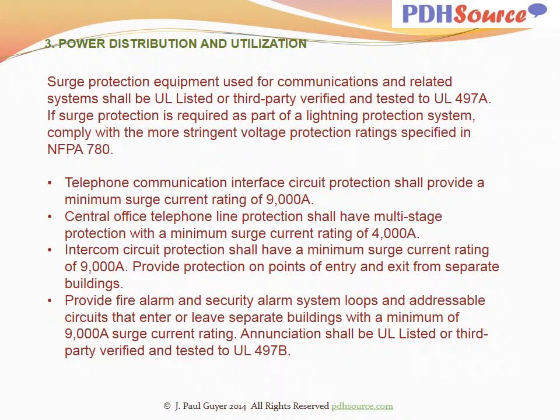Surge protection equipment used for communications and related systems shall be UL listed or third party verified and tested to UL497A. If surge protection is required as part of a lightning protection system, comply with the more stringent voltage protection requirements specified in NFPA 780. Telephone communication interface circuit protection shall provide a minimum surge current rating of 9,000 amps. Central office telephone line protection shall have multi-stage protection with a minimum surge current rating of 4,000 amps.